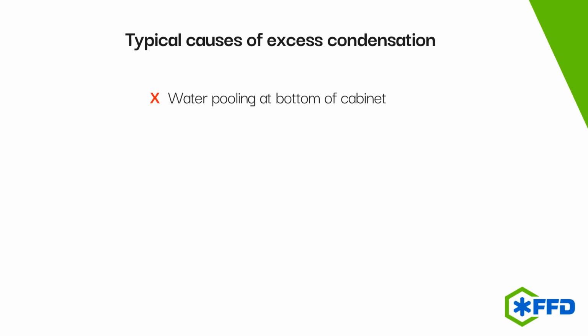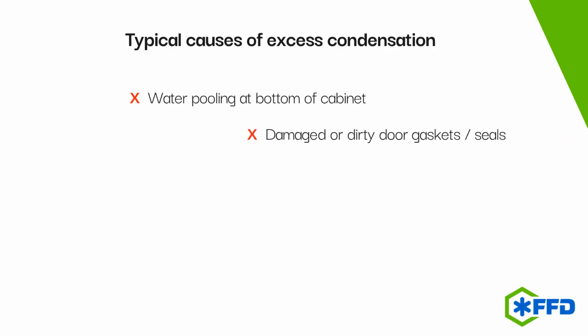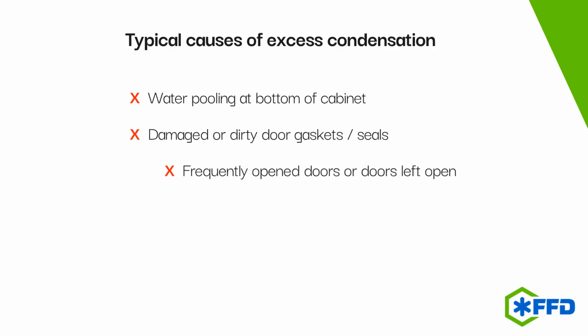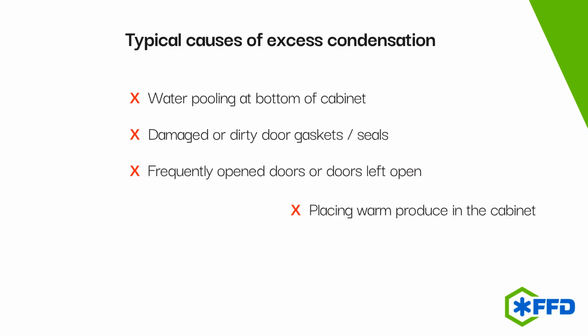Typical causes of excess condensation are water pooling at the bottom of the cabinet, damaged or dirty door seals, frequently open doors or doors left open, and placing warm produce in the cabinet.